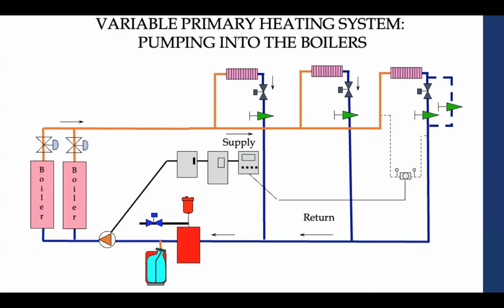Have some type of drive, variable frequency drive attached to my distribution pumps, because as loads change and control valves start to close down, why do I need to keep running that pump as if it's 100% design conditions when loads are changing? I might have some type of DP, differential pressure sensors, remotely located out in the building. And they're sensing a change in flow, change in pressure. They'll feed that back to the drive, which will in turn affect the operation, the speed, the RPMs, which means the flow rate and head that this distribution pump can develop.